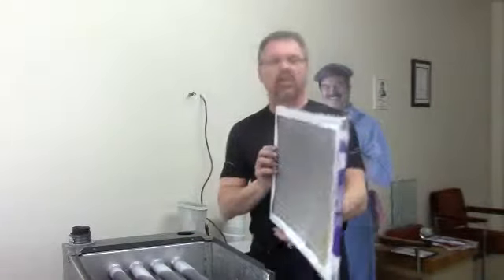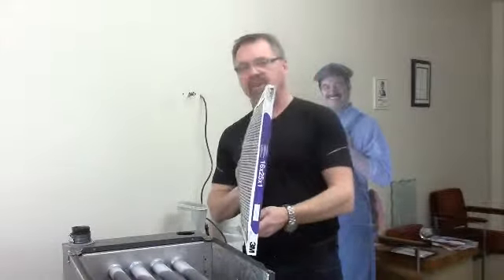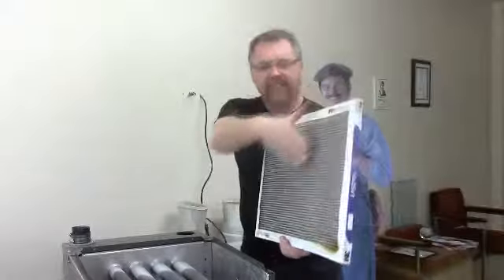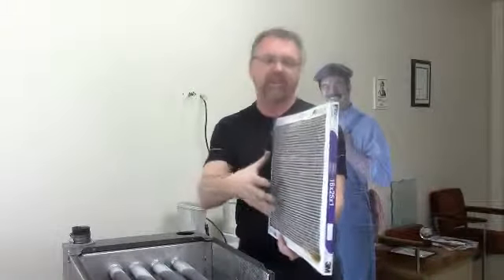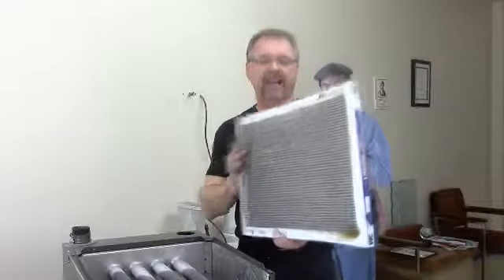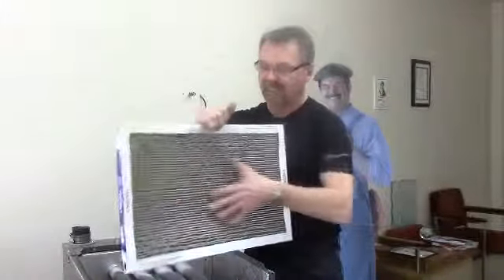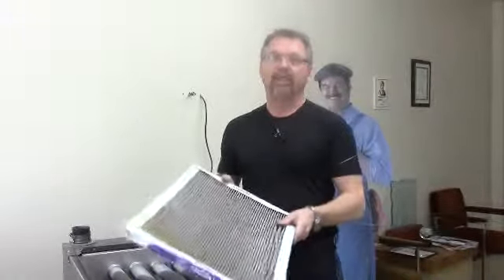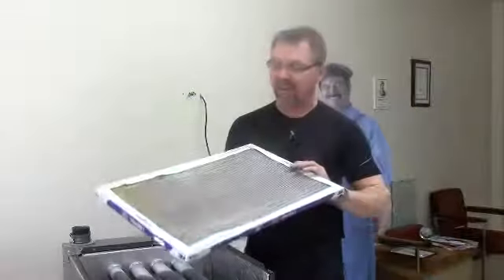Most 1-inch filters, you're going to have to change them every 30 days, sometimes more. If you need to do it more, maybe you should be looking at duct cleaning. For instance, here's a typical 1-inch filter. It is dirty, but it isn't that dirty. But you can see that it is bowed out here. That means the fan's trying to suck air through the filter and it's not getting the job done. That's why it's bowing the filter in. So that's not a good sign. That means we have air restrictions. So this filter was desperately in need of changing even though it wasn't all that dirty.